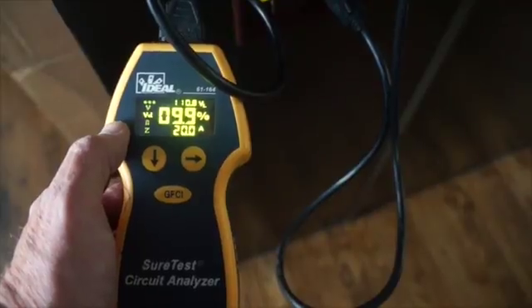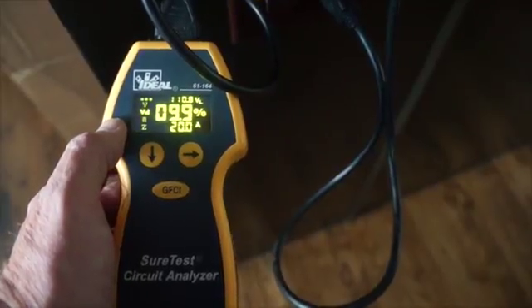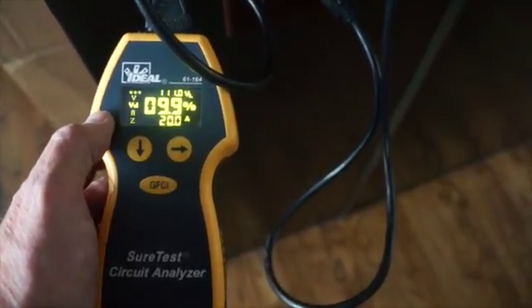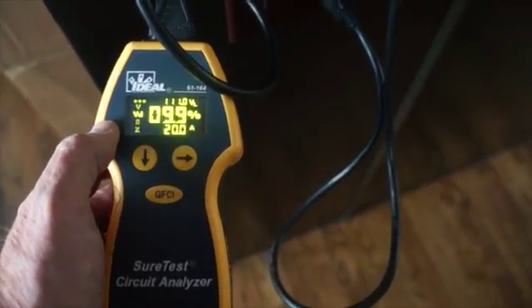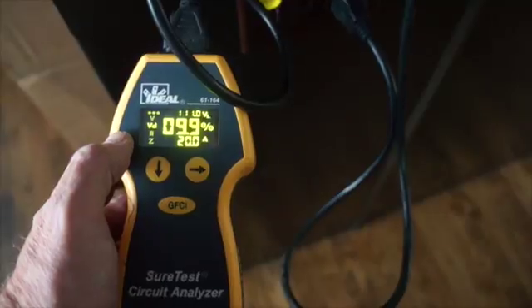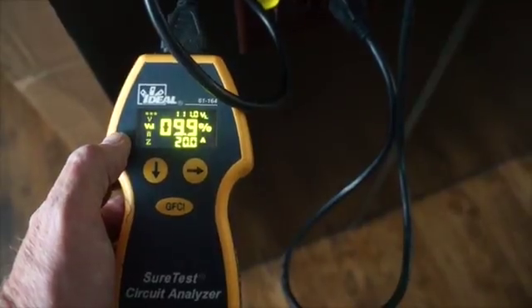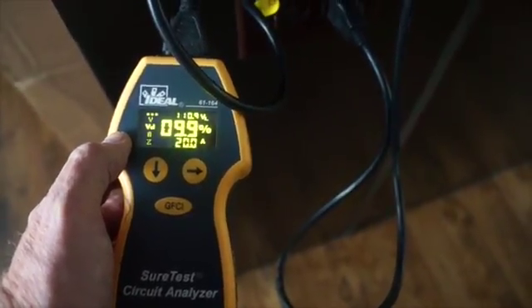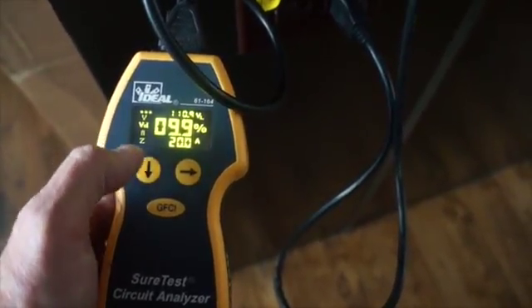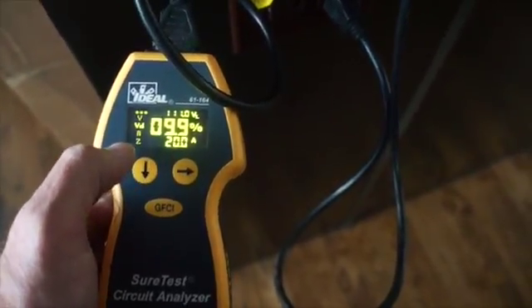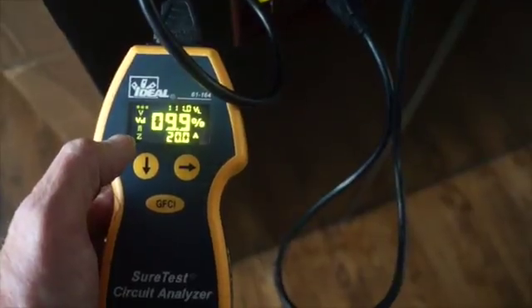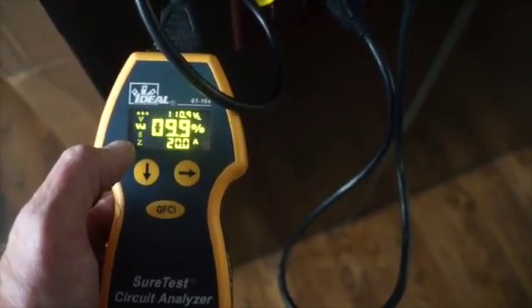You can see here we've got 9.9% drop in voltage. That's quite huge. If you plugged a heavy duty item in here, like a waffle maker, you could actually start a fire. So every inspection we do, we routinely test for voltage drops.